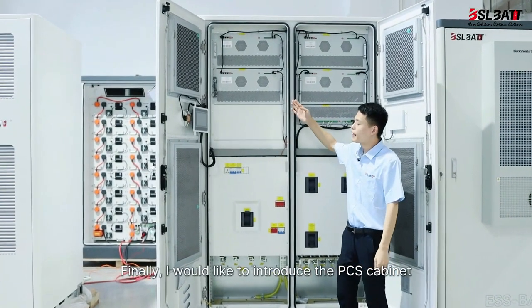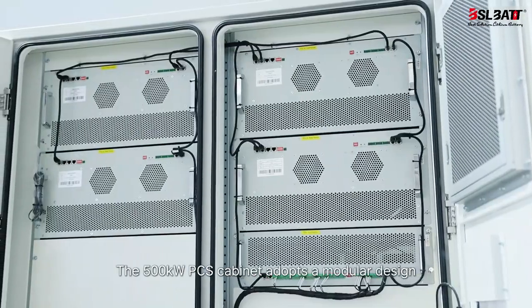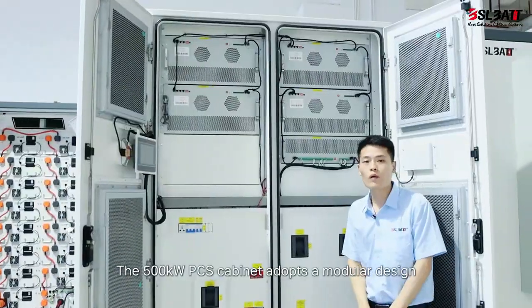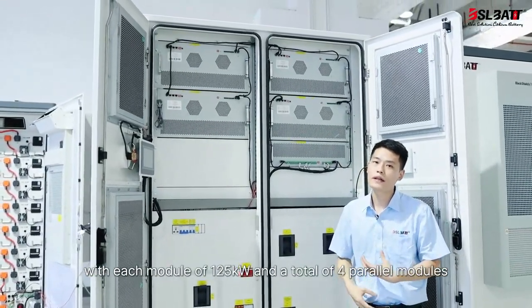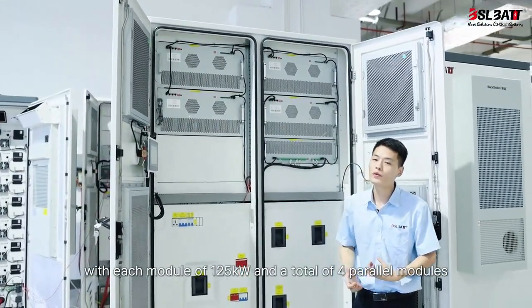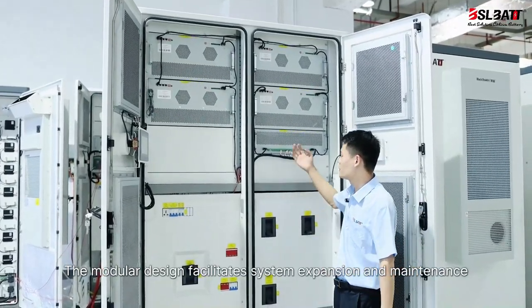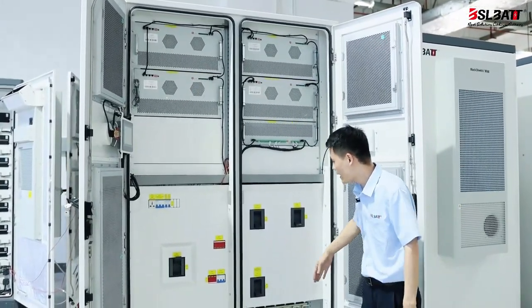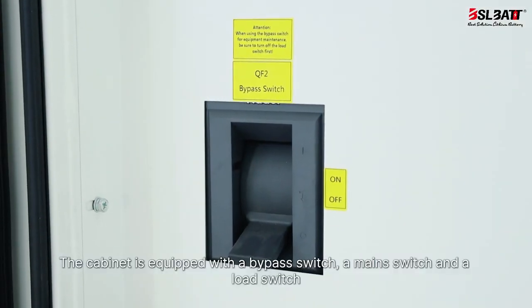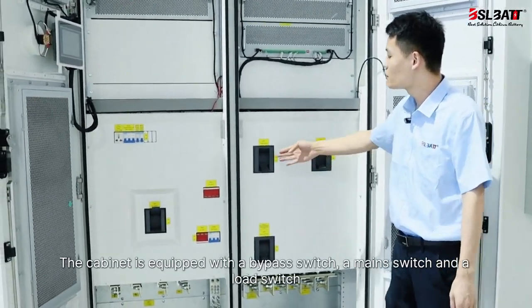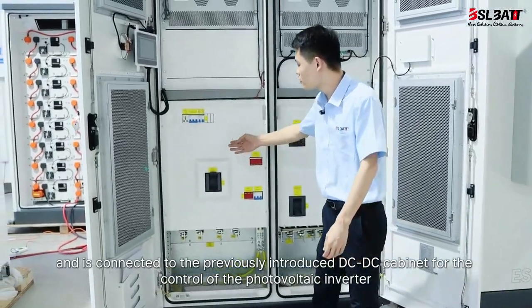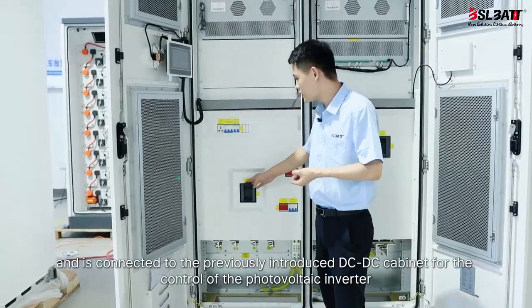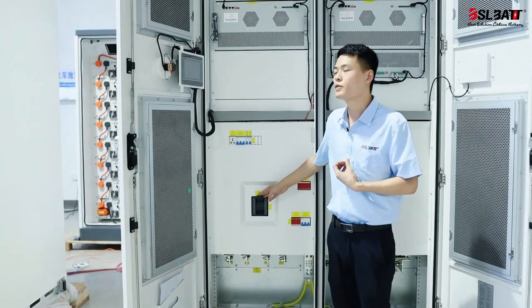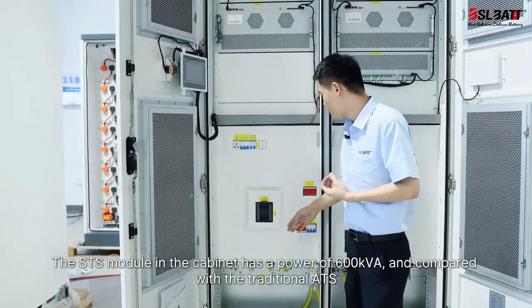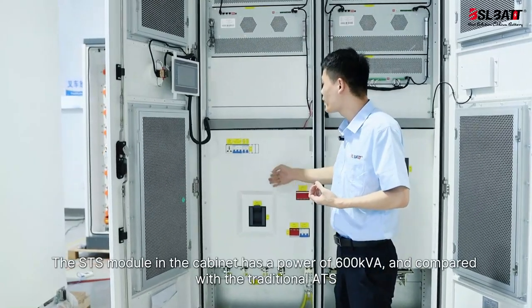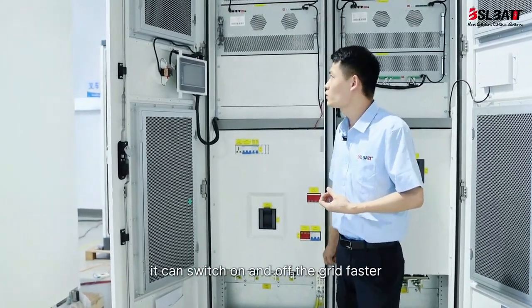Finally, I would like to introduce the PCS cabinet. The 500 kilowatts PCS cabinet adopts a modular design, with each module of 125 kilowatts and a total of 4 parallel modules. The modular design facilitates system expansion and maintenance. The cabinet is equipped with a bypass switch, a main switch and a load switch, and is connected to the previously introduced DC-DC cabinet for the control of the photovoltaic inverter. The STS module in the cabinet has a power of 600 kW, and compared with the traditional ATS, it can switch on and off the grid faster.